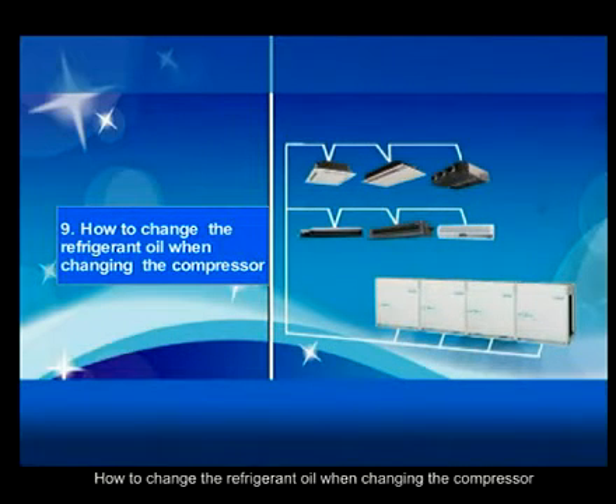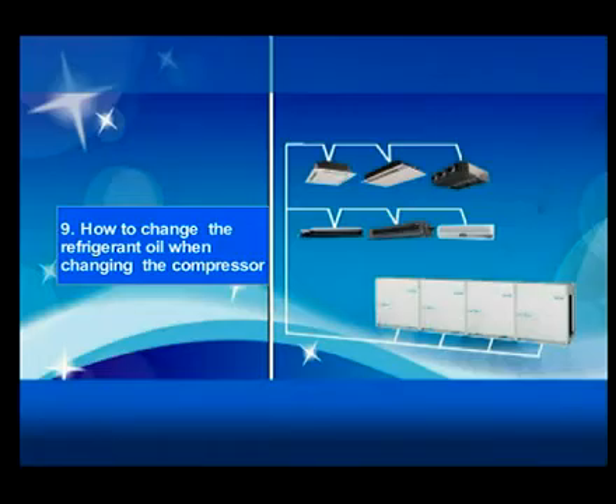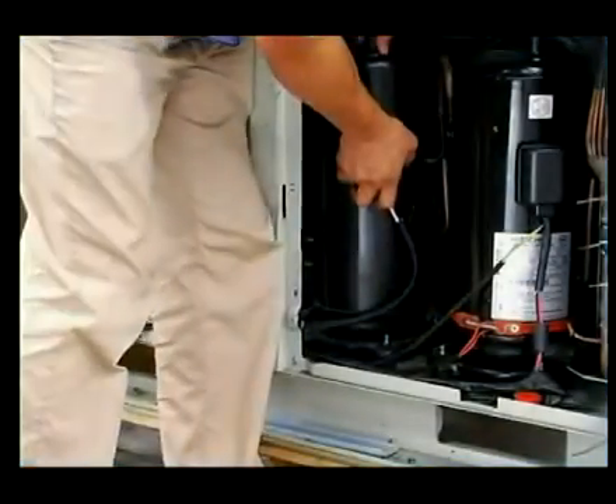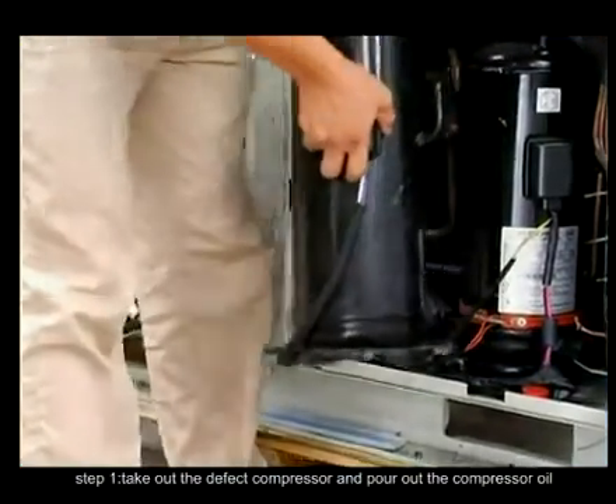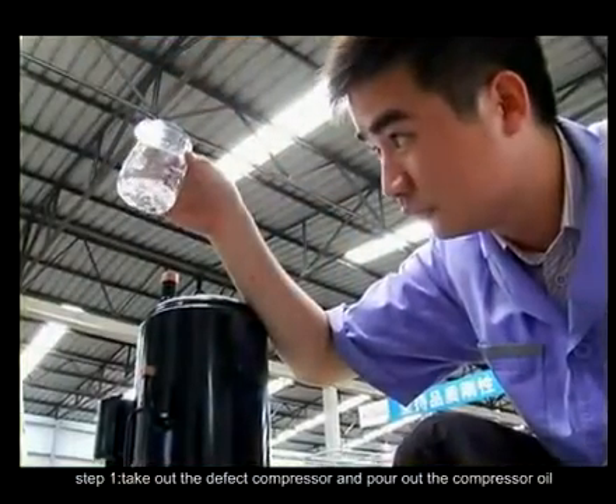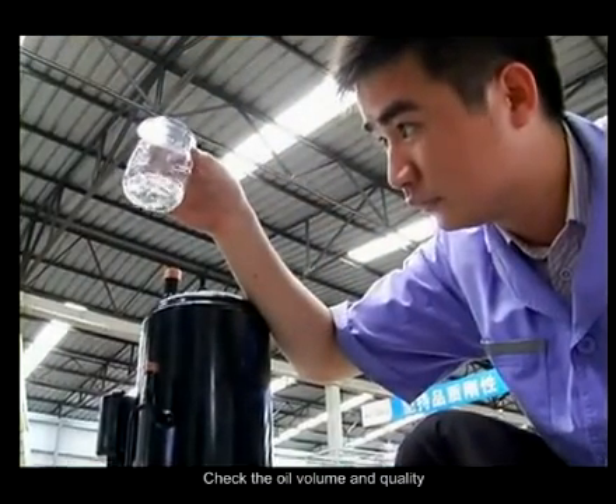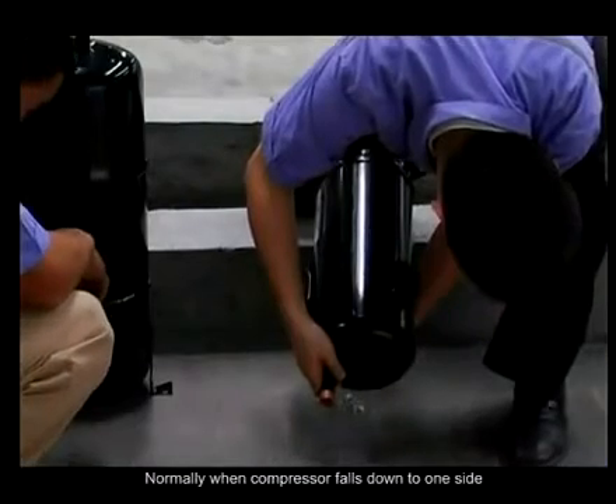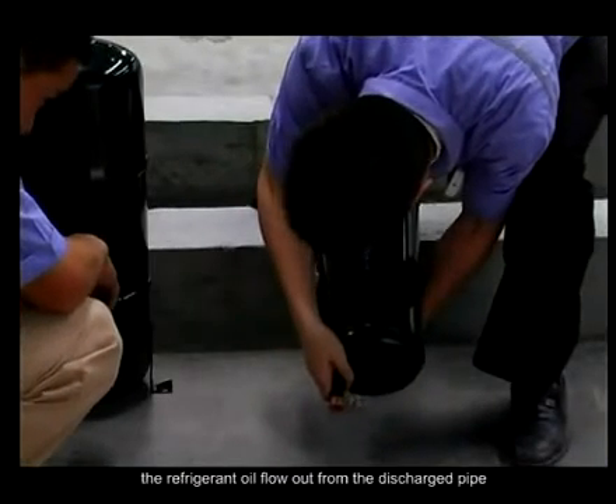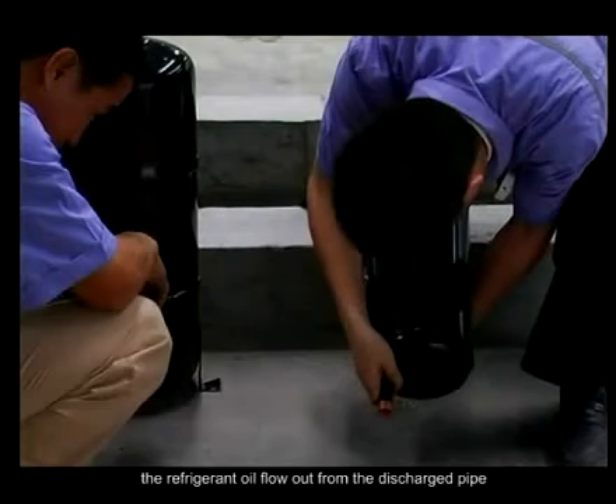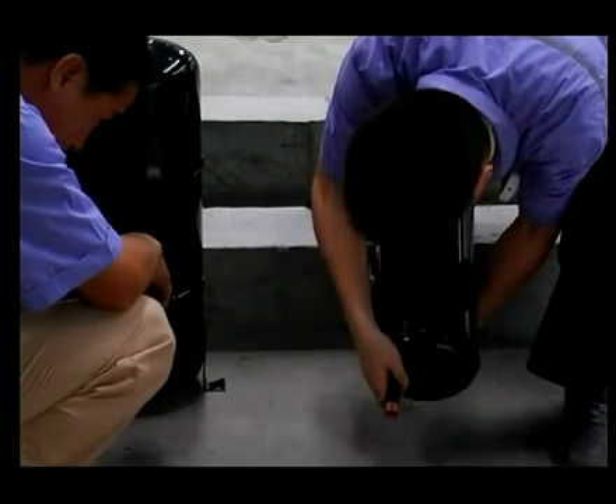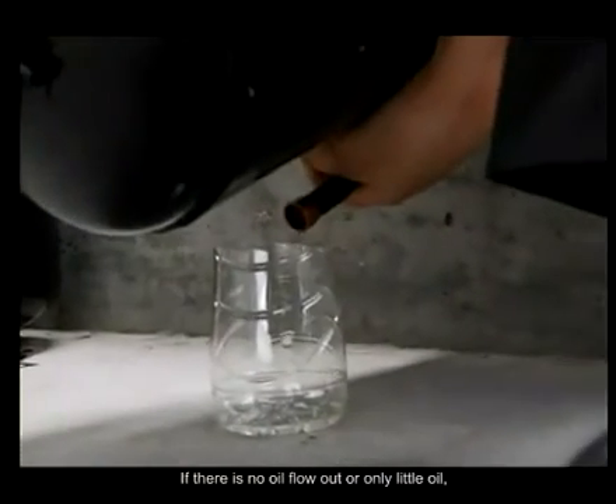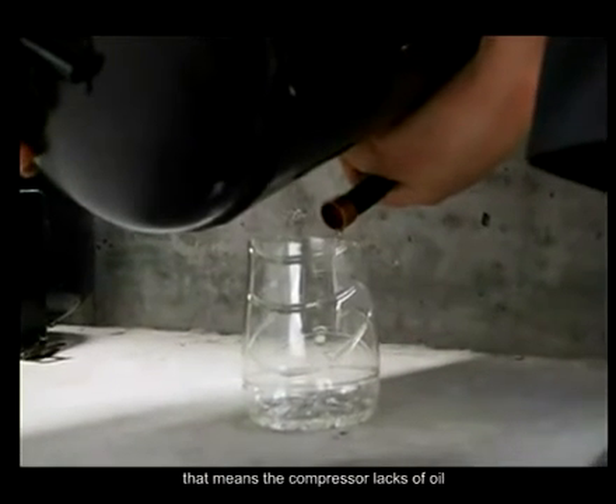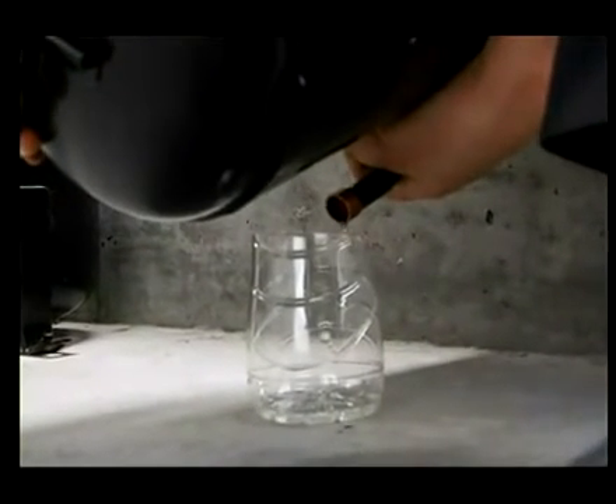How to change the refrigerant oil when changing the compressor. Step 1. Take out the defective compressor and pour out the compressor oil. Check the oil volume and quality. Normally, when the compressor is tipped to the other side, the refrigerant oil flows out from the discharge pipe. If no oil or only a little oil flows out, that means the compressor lacks oil.